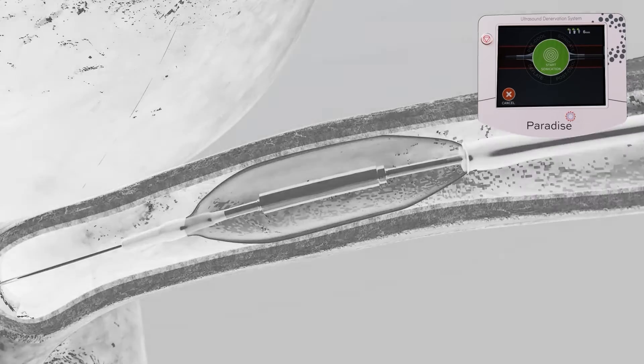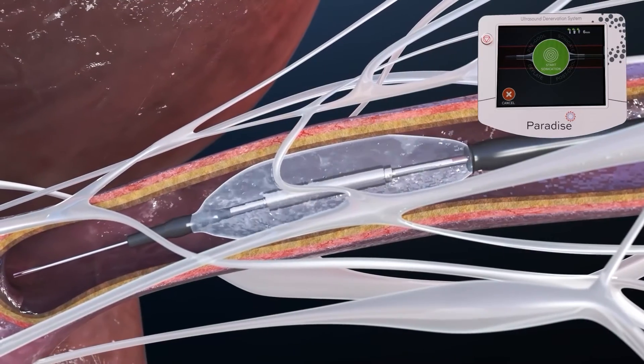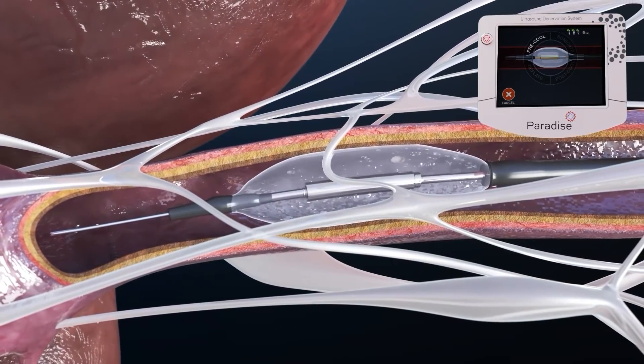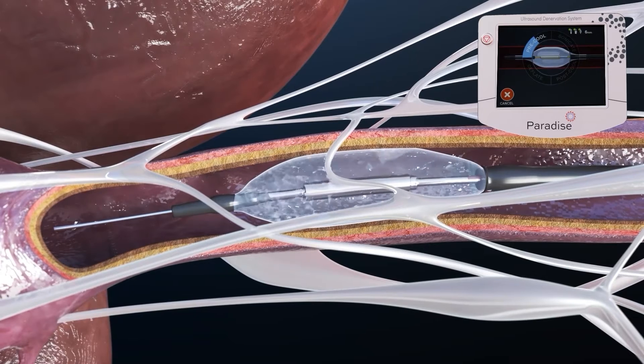Once apposition is confirmed, the catheter is ready to sonicate and deliver 360 degrees of ultrasound energy to a targeted depth of one to six millimeters, reaching 80% of the sympathetic nerves around the artery.